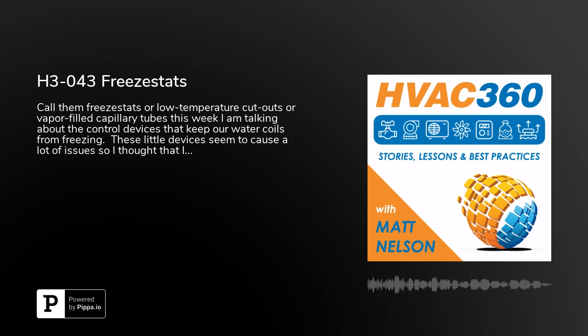So now we have the critical component, and I guess this probably comes into play most often, or maybe this stems from a lot of the questions. Where do you put the darn thing? Where does the sensing element go? Now, typically, and we're talking air handling units here, you're either going to have 1 or 2 coils. Typically, if you have one coil, it's going to be on the downstream side of that coil, and in general, it's going to be on the downstream side of any coil. So if you have a heating coil and then a cooling coil, with the heating coil in the preheat position, you're going to have it on the downstream side of that heating coil. So off the heating coil, you're going to have that Freezestat to protect the cooling coil. If you just have a cooling coil, you're going to put it on the downstream side of that cooling coil.